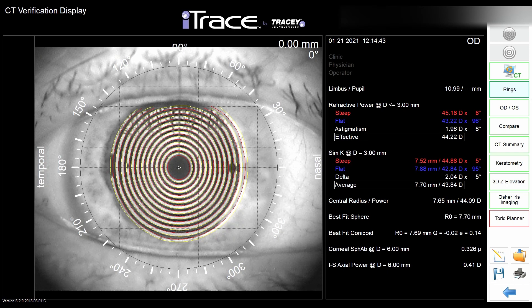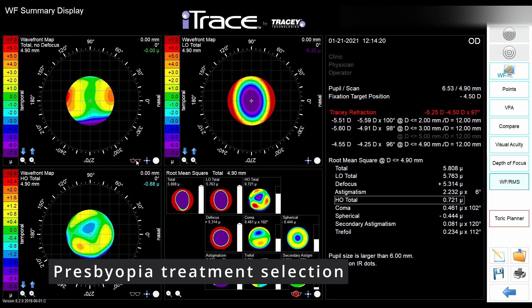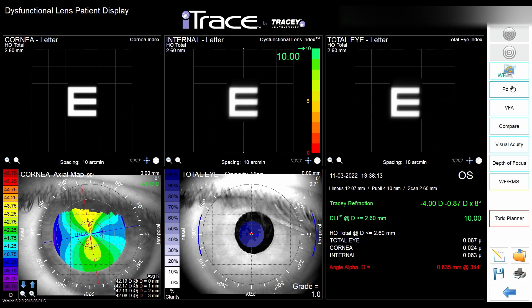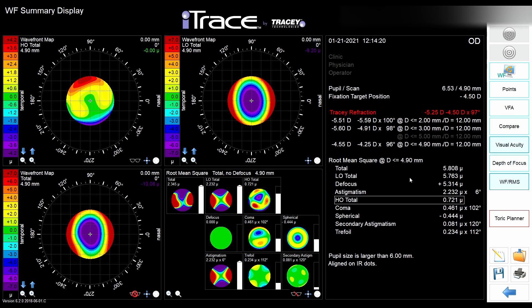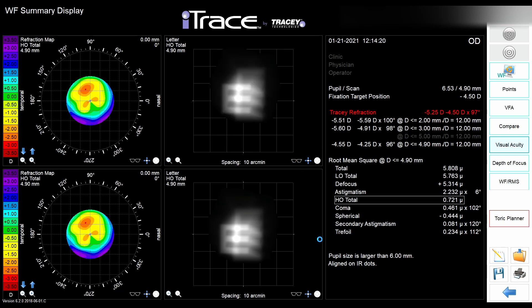Another group of patients — thanks to the Dysfunctional Lens Index — are patients being considered for presbyopia laser treatment. For those patients, you want to see whether they have no lens problems and whether the lens is clear. Having an objective index measurement is very important for deciding whether clear lens exchange or presbyopia correction makes more sense. This machine really offers an objective way of doing things.